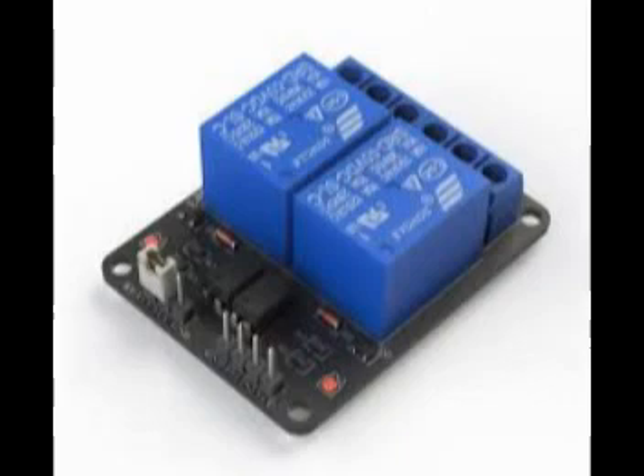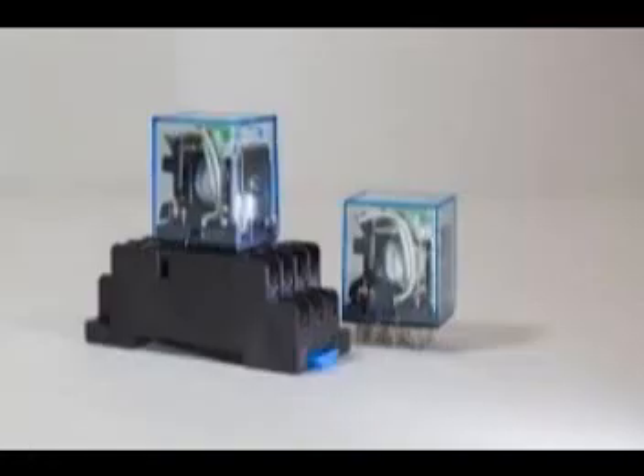Yeah, precisely. They either close, which completes a separate circuit, or they open, which breaks it. And one of the key benefits here, the document really points this out, is the electrical isolation. The control circuit, the one powering the coil, is completely separate, electrically isolated from the circuit being controlled by those contacts. That makes total sense. Keeps things safe, stops electrical noise jumping between circuits, that kind of thing.